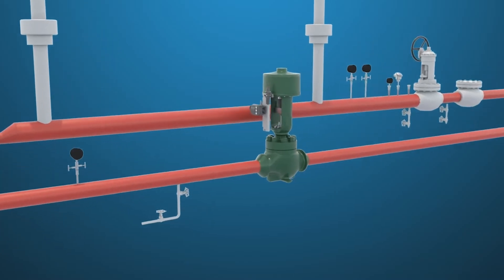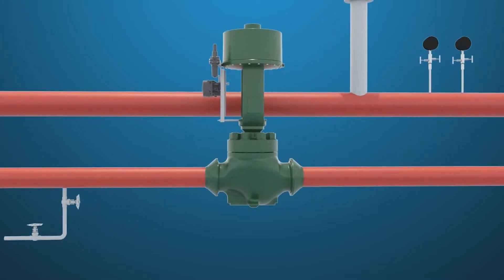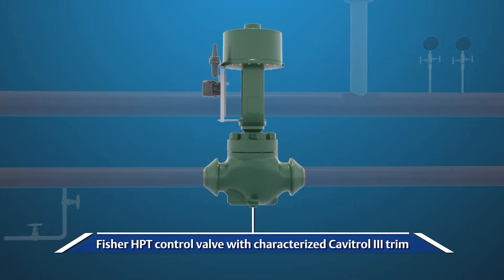When a single valve is used, a special characterized cage is required to prevent cavitation damage. The lower travels of the cage use anti-cavitation trim for the startup and low load conditions. The higher travels of the cage use larger drilled holes or windows to provide the flow rates needed for normal operation.